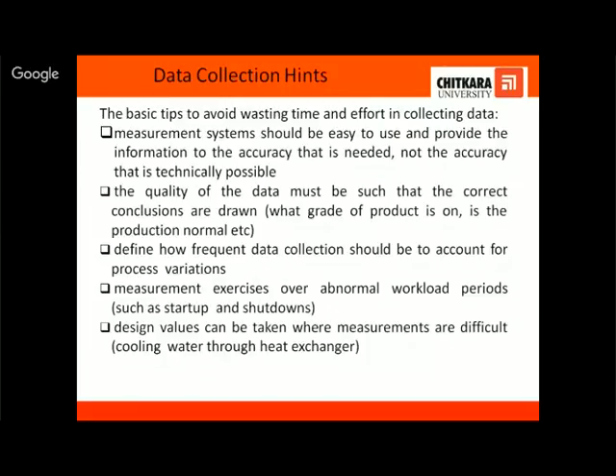Then what data has to be collected when the machine is starting and when the machine is shut down, because during the starting it may draw a large amount of current, and then what is the power flow when the machine gets shut down. And sometimes it's not possible to take the measurements. In those cases we can take the design values or the specifications from the nameplates.